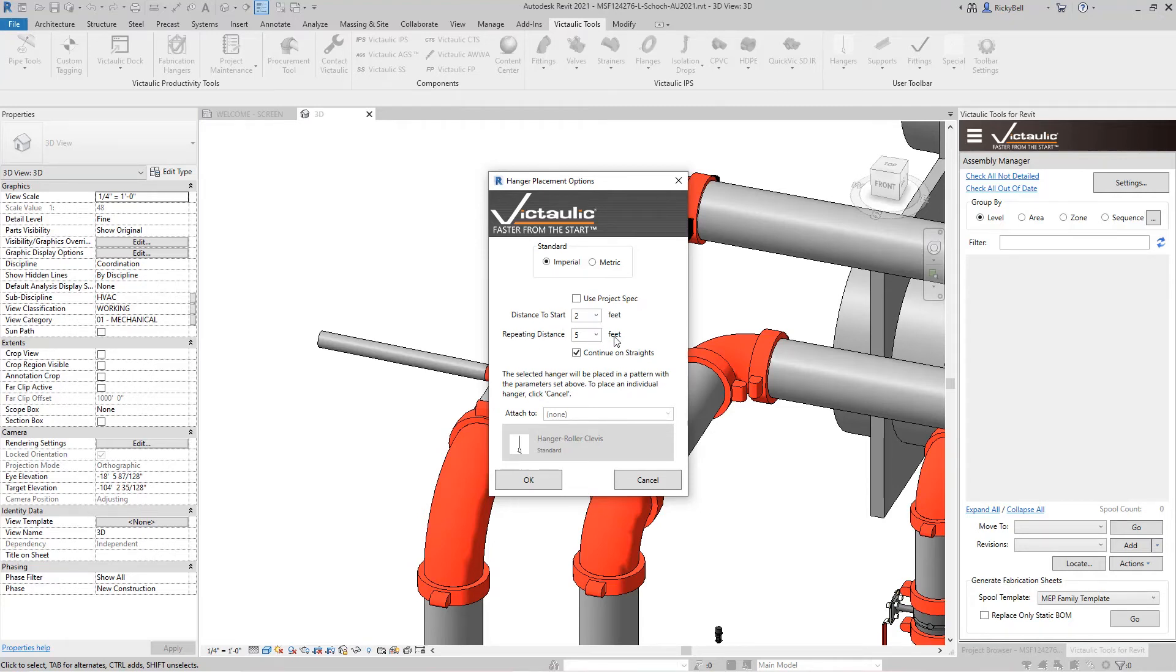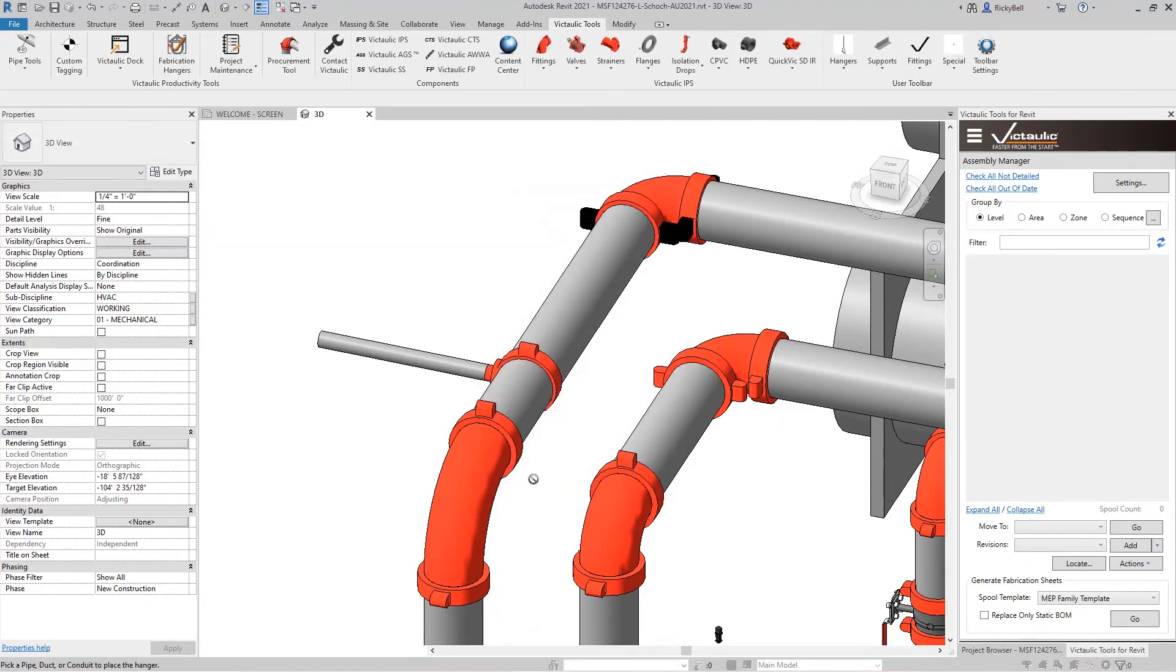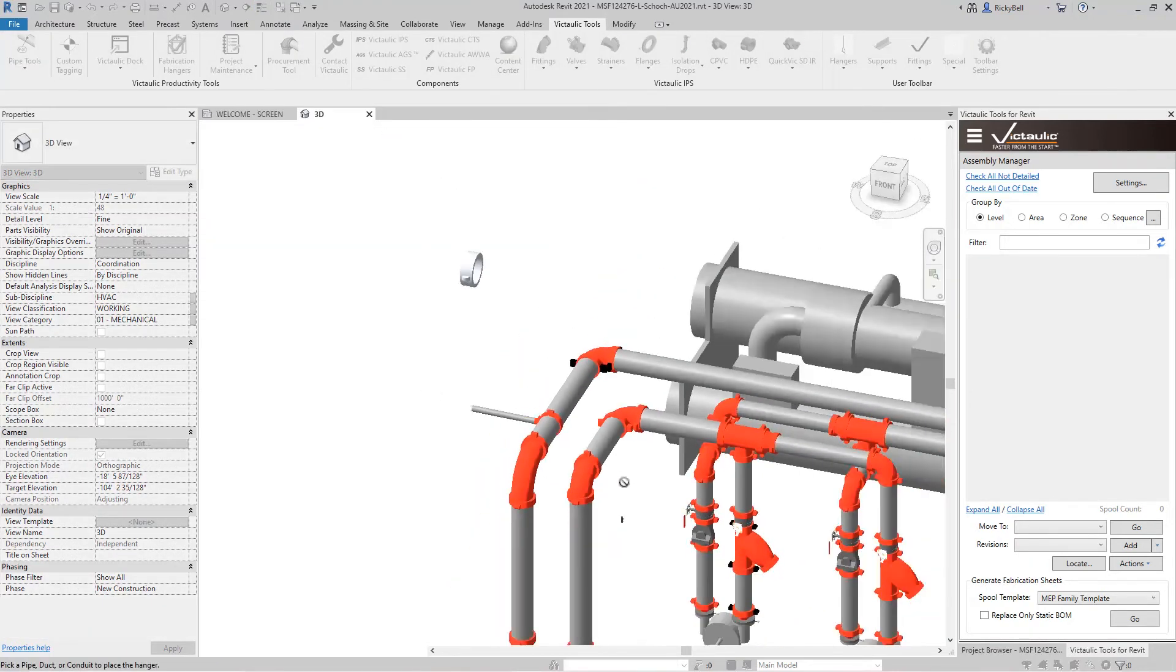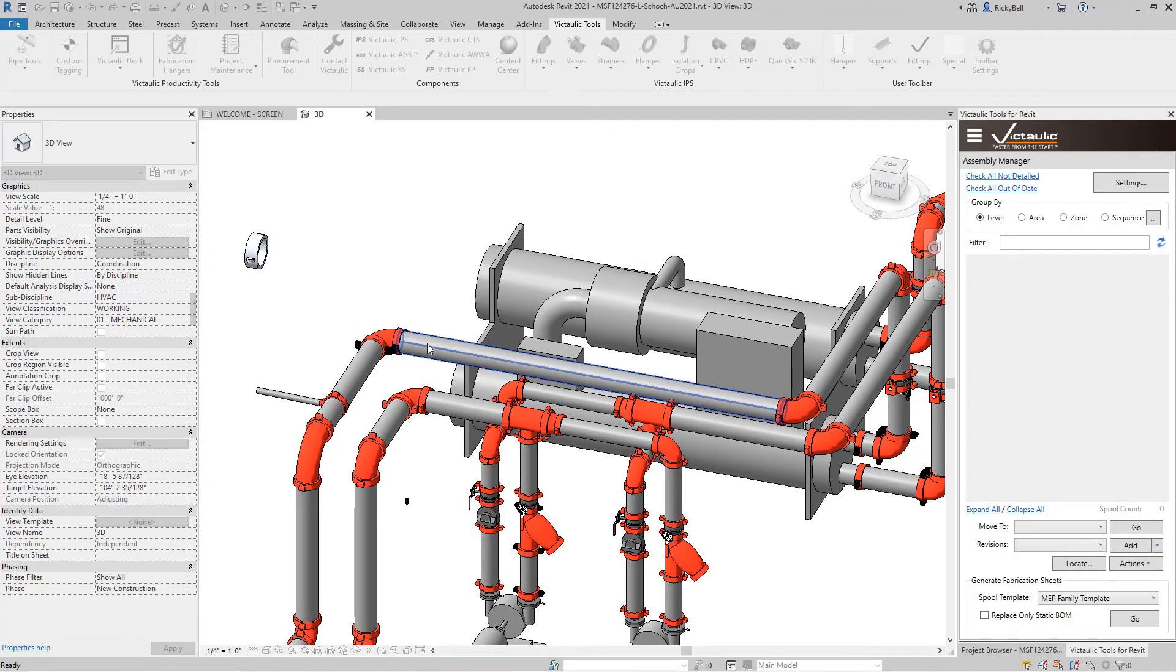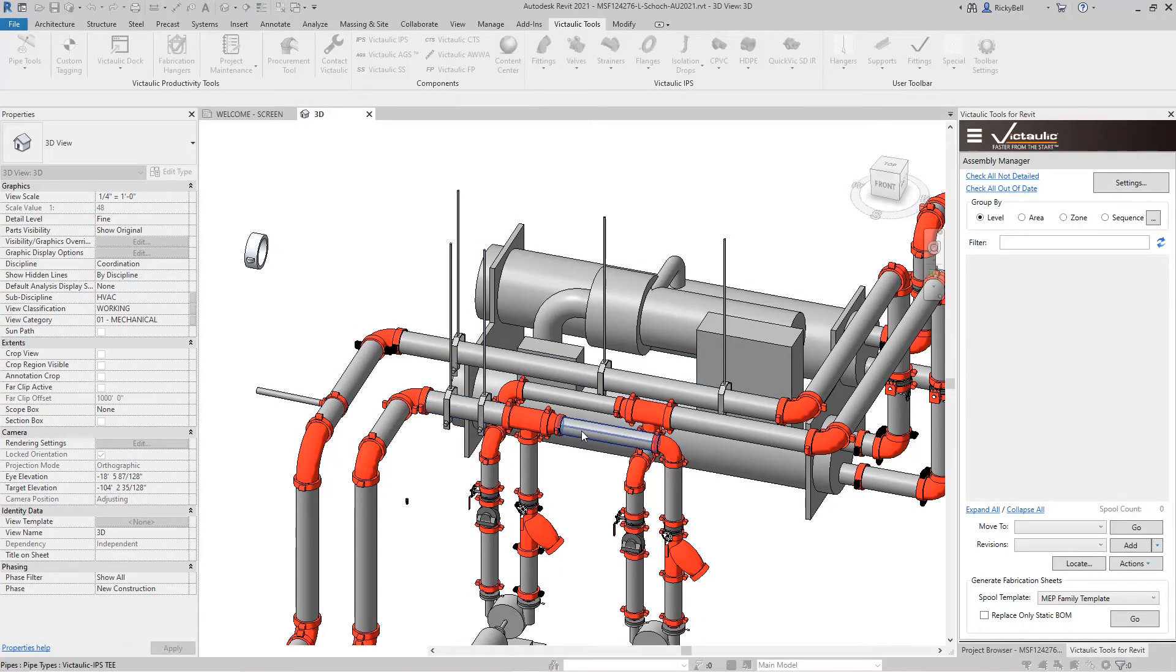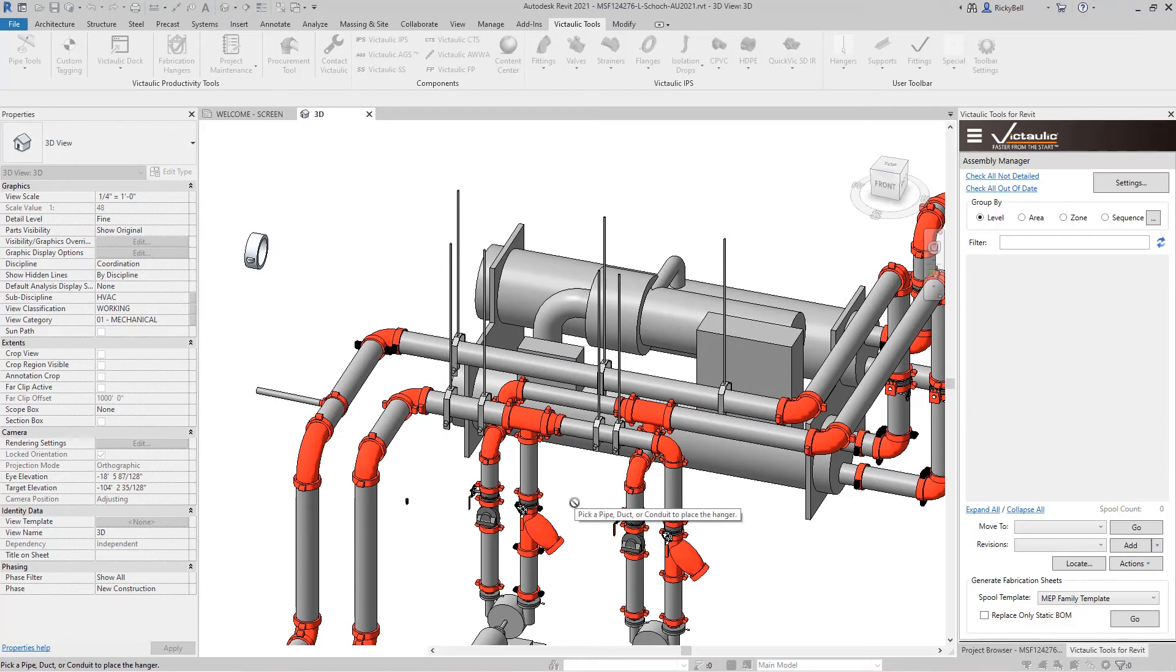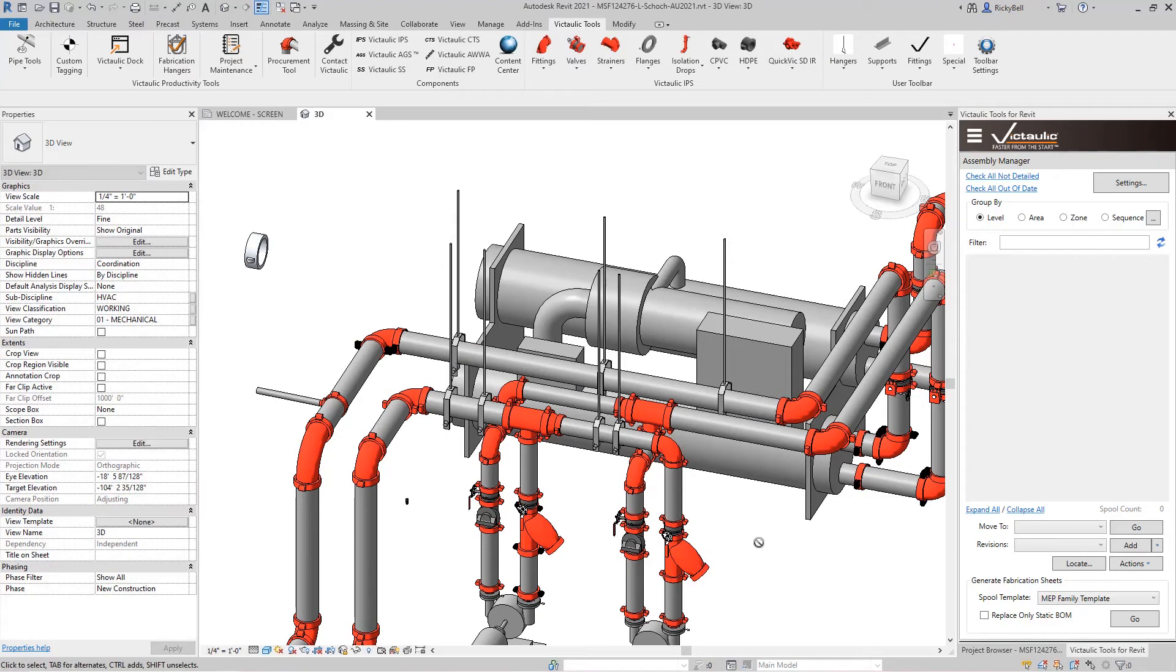But you basically give it dimensions like the distance from the start and the repeating distance. And this is going to place hangers on any piece of pipe that you click. So I'll click OK and back out a little bit. And as I click on each of these pieces of pipe it will place the appropriately sized hanger following the rules that we gave it. Which at that time was two feet from the beginning and five feet repeating.